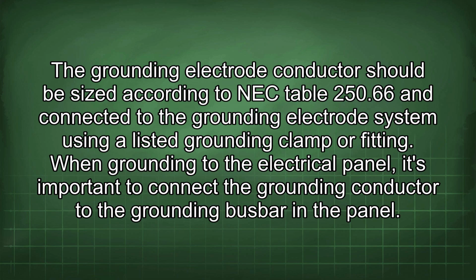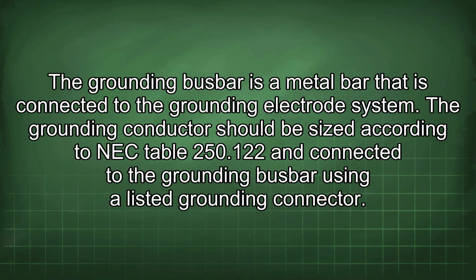When grounding to the electrical panel, it's important to connect the grounding conductor to the grounding busbar in the panel. The grounding busbar is a metal bar that is connected to the grounding electrode system. The grounding conductor should be sized according to NEC Table 250.122 and connected to the grounding busbar using a listed grounding connector.